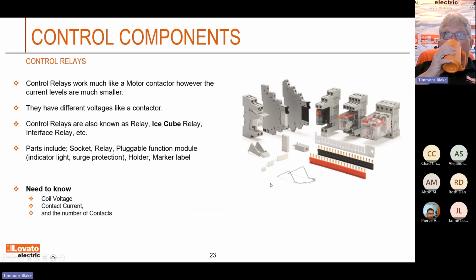Let's talk about control relays now a little bit. A control relay works a lot like a motor contactor. You still have that little electric magnet in there, and you're triggering a set of contacts. You're going to turn something off and on. And it's good for isolation. They have different voltages like the contactor. You can power them with 24 volts DC, 24 volts AC, 110 volts, 48 volts, 480 volts. You just got to look. When you look at a relay, you got to realize you have the coil voltage, you have the contact current, and the number of contacts. Okay.